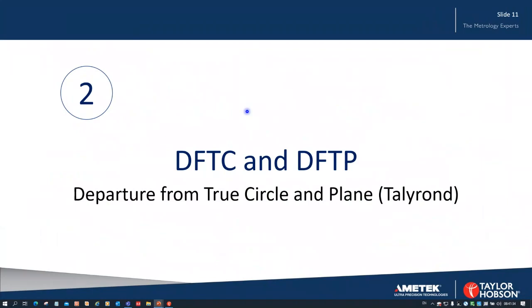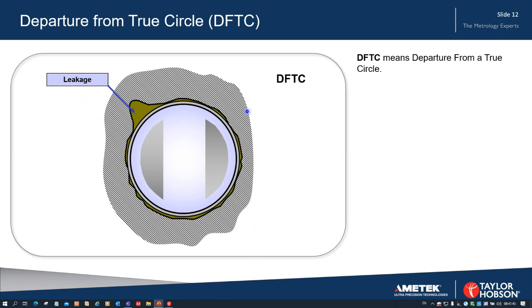Let's have a look now at departure from true circle and departure from true plane on a roundness instrument — in this case Taylor Hobson's Talyrond systems. DFTC means departure from a true circle; over the full 360 degrees it's the same thing as roundness — this is, if you like, local roundness. We might have a situation with a fuel pipe where if there is an error at one point, that's where leakage may occur. So we might have a specification over the whole circle which passes, but also a separate specification for a particular area relevant to leakage.